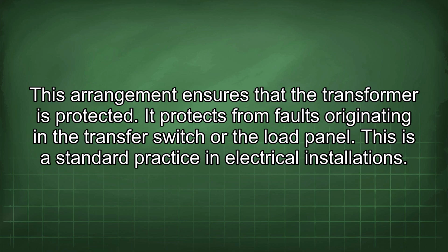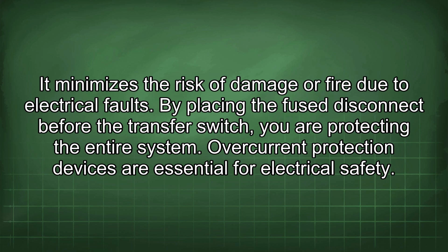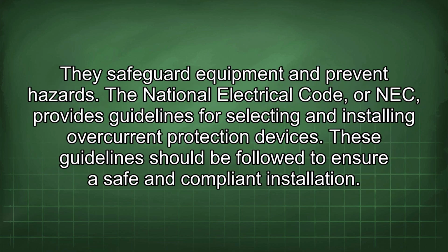This is a standard practice in electrical installations. It minimizes the risk of damage or fire due to electrical faults. By placing the fused disconnect before the transfer switch, you are protecting the entire system. Overcurrent protection devices are essential for electrical safety. They safeguard equipment and prevent hazards.